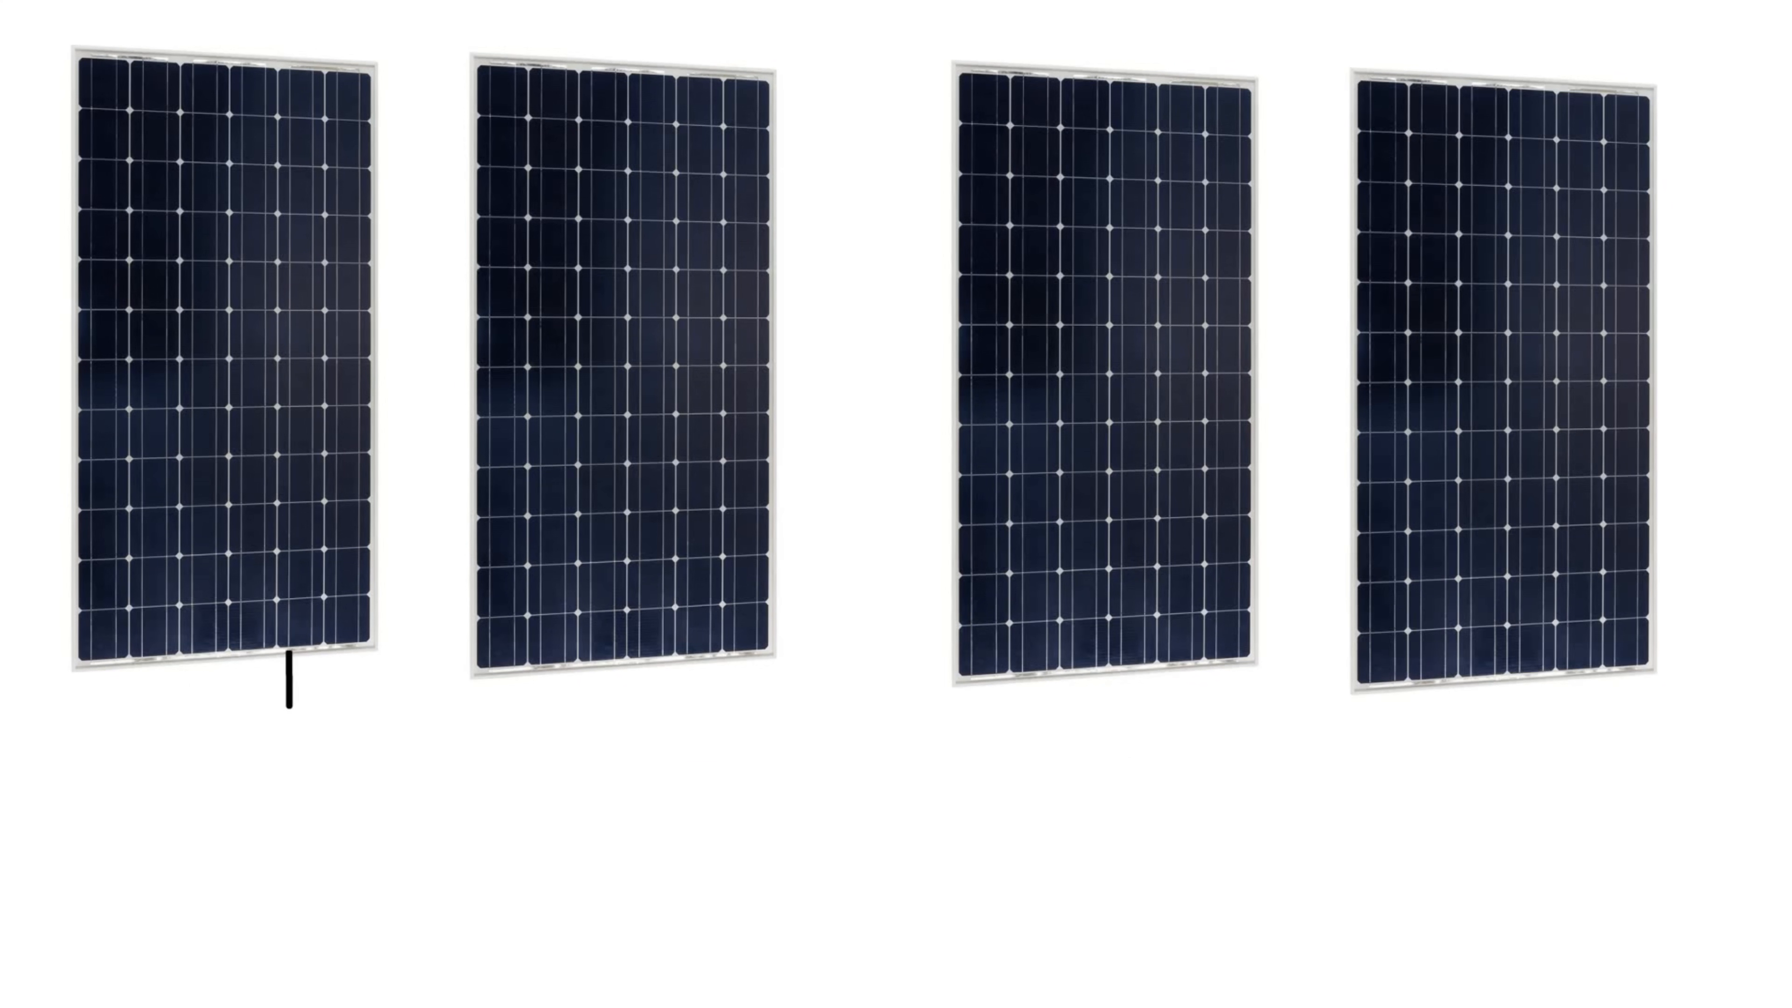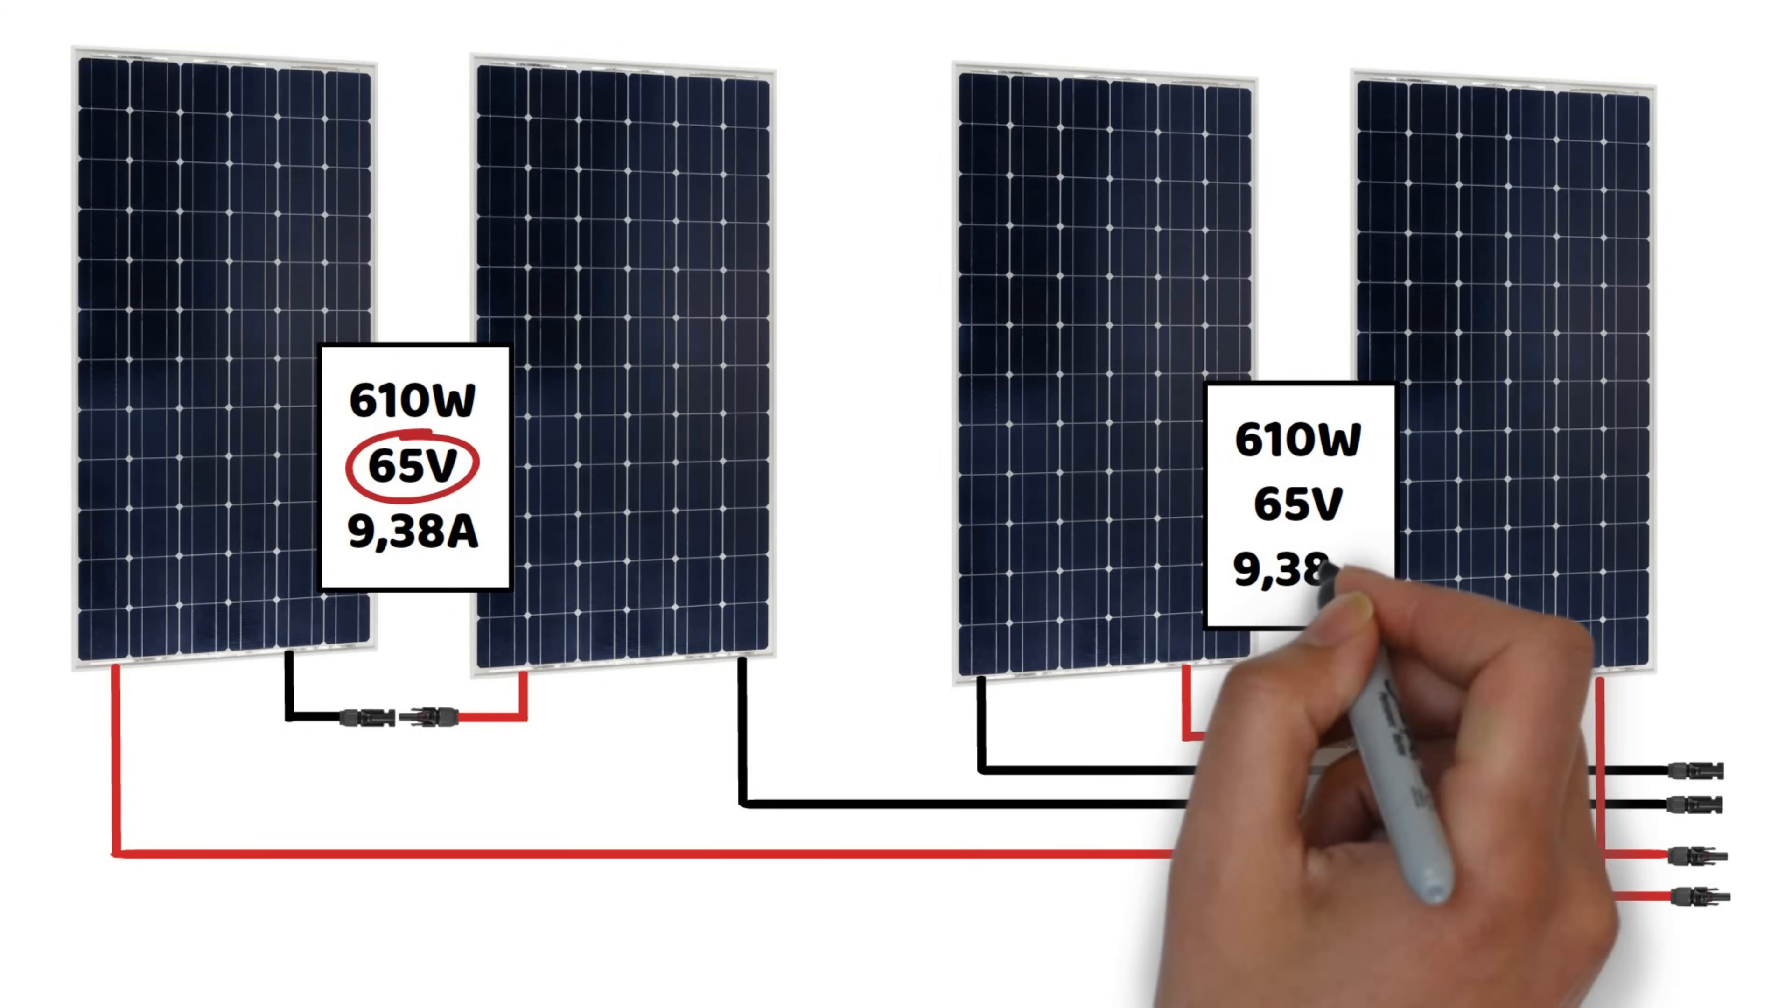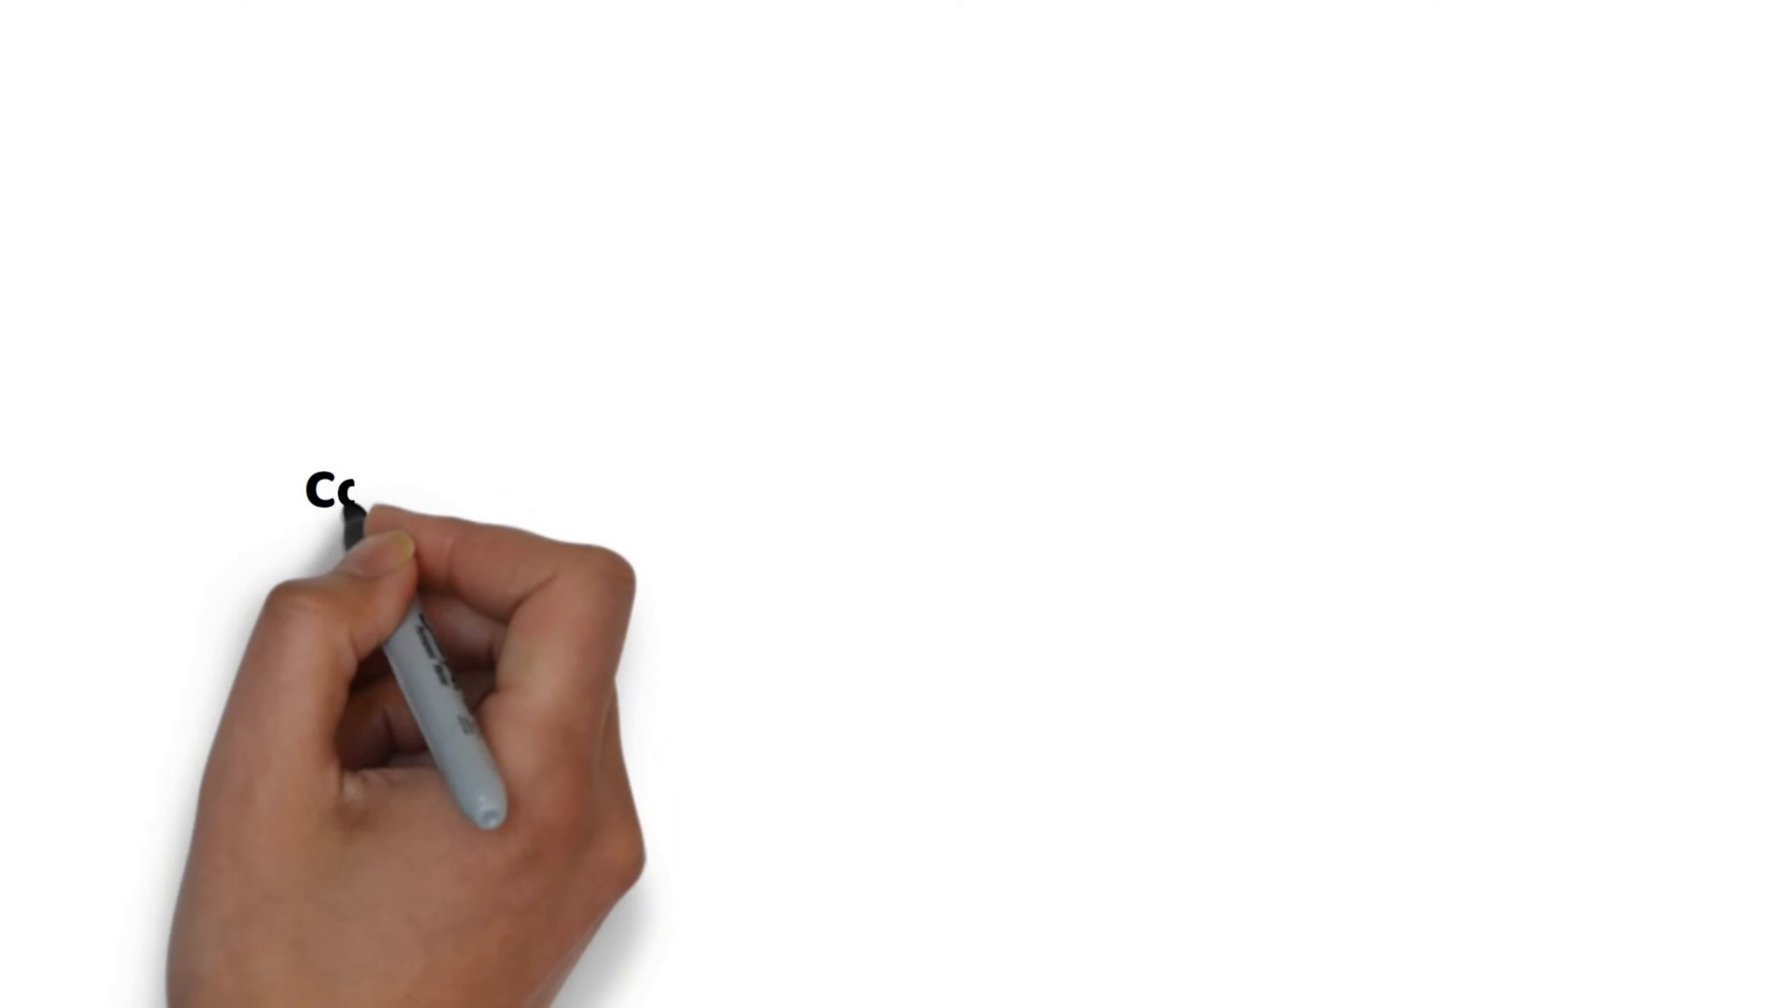We also covered the mixed series parallel configuration. For this example, we'll use four panels to make it clearer. Here, we'll have two pairs of panels connected in series, and then these two sets will be connected in parallel. Let's stick with the same panels as before. In this setup, we'll have 32.5 volts plus 32.5 volts, resulting in 65 volts with a current of 9.38 amps and a power of 610 watts for each series connected pair. The same will apply to the second set, as we are still using identical panels. Now, when we connect these two sets in parallel, the voltage will remain unchanged at 65 volts, while the current will increase from 9.38 amps to 18.8 amps. This will give us a total power of four times 305 watts, or 1220 watts. You can use connectors here, since the current is still relatively low, or you can opt for bus bars. Once again, if you'd like to better understand the advantages and disadvantages of series versus parallel connections, I encourage you to check out my previous video on the channel.